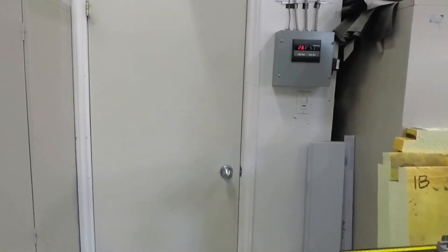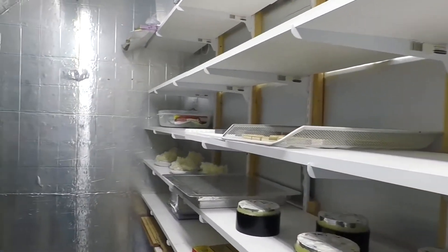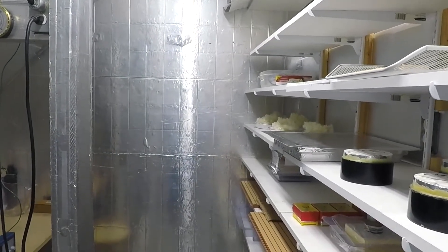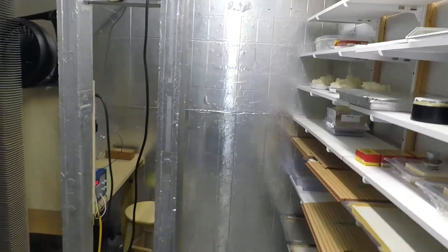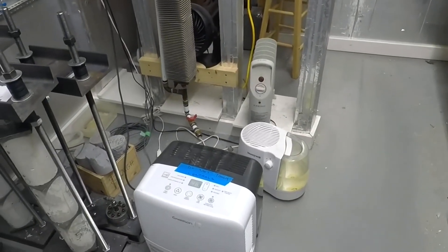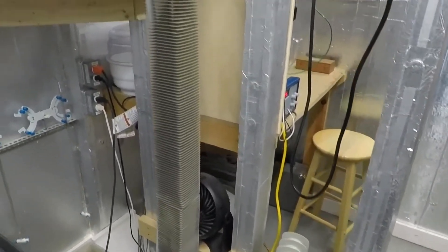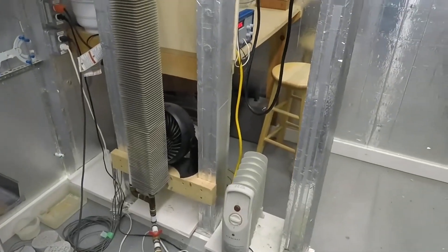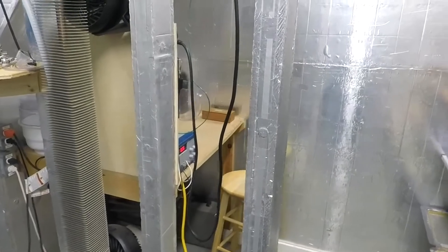Let's go into the climate chamber that we use. The important part about this particular room is that it is controlled at a very steady temperature and humidity. We actually have conditioning equipment here that does humidification, dehumidification, cooling through this finned tube unit, heating through the electric heater, and there's even a few other little features that we use.